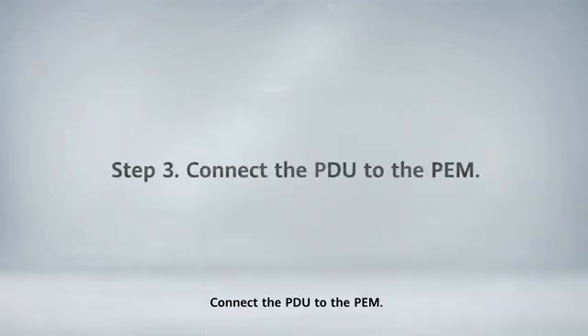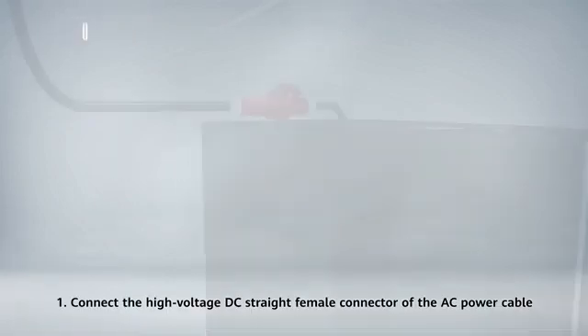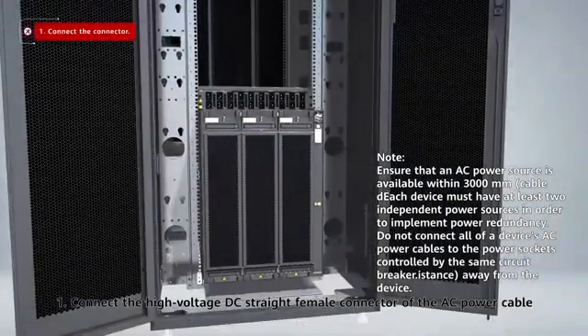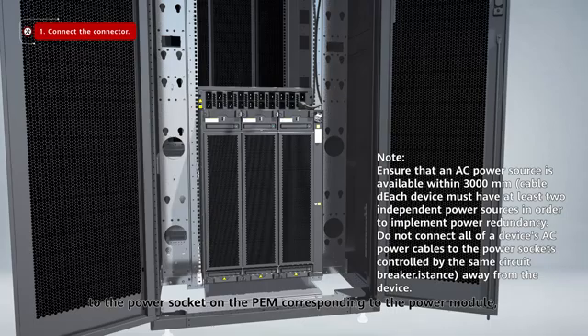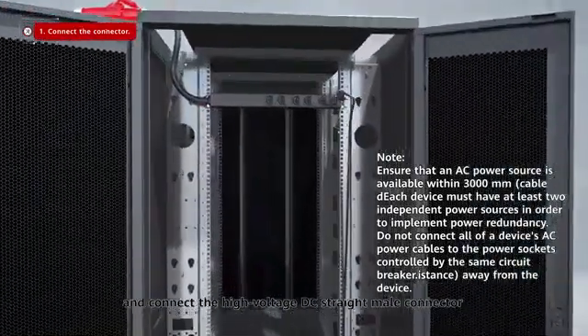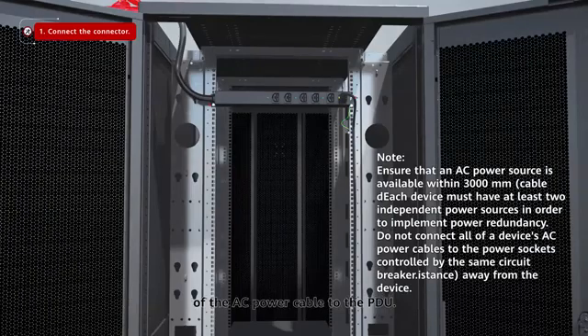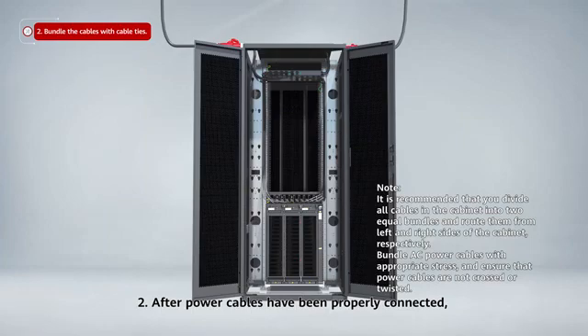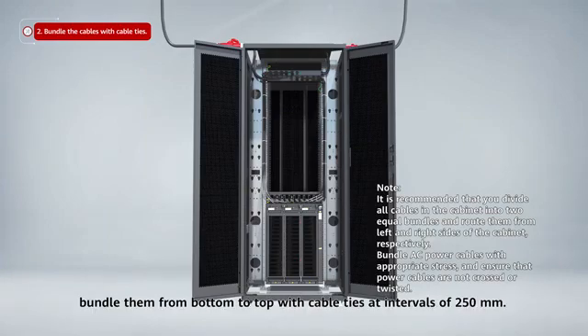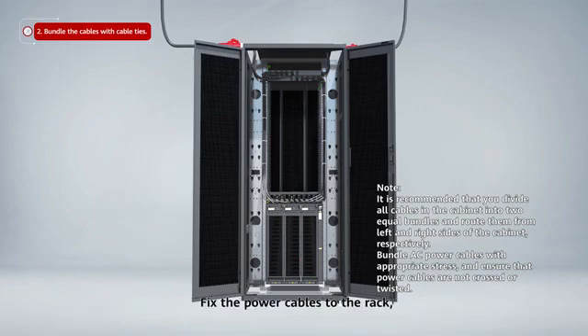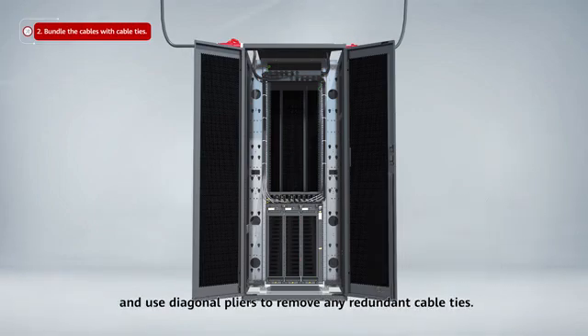Connect the PDU to the PEM. 1. Connect the high-voltage DC straight female connector of the AC power cable to the power socket on the PEM, corresponding to the power module, and connect the high-voltage DC straight male connector of the AC power cable to the PDU. 2. After power cables have been properly connected, bundle them from bottom to top with cable ties at intervals of 250 mm. Fix the power cables to the rack and use diagonal pliers to remove any redundant cable ties.